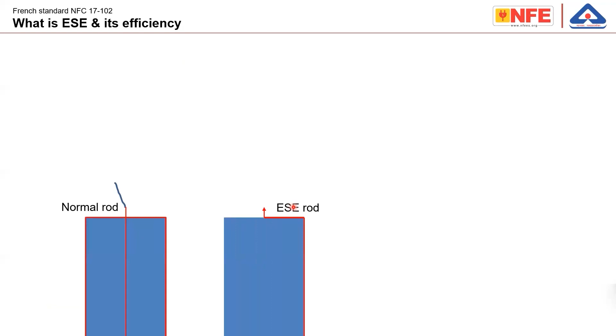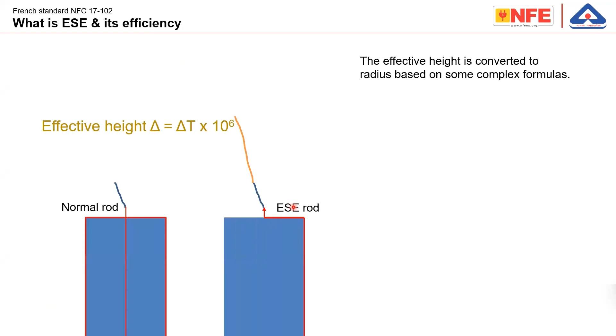So the theory of these protection devices, these manufacturers say, is that a normal rod is able to emit a streamer of, let us say, X distance. The early streamer emission device is faster, it is more capable, and it is able to emit a streamer of a higher distance. So this theory is never accepted anywhere in the world because the ESE vendors could not show it practically to anybody. Only in their closed laboratories they test and they claim these particular figures, but on several occasions it is proven that the claims are totally wrong. So they say there is a delta t time advancement, then there is a complicated calculation, and based on the calculation they say, since my rod is faster, I can protect 108 meters or 102 meters.